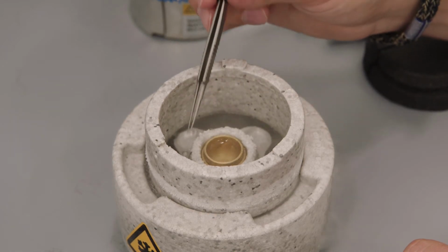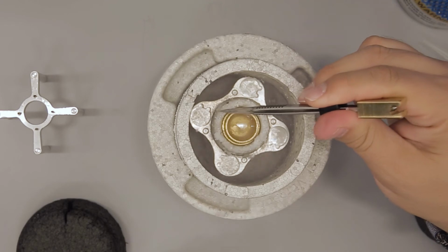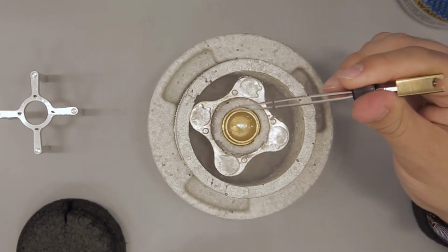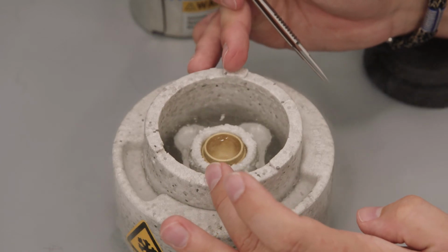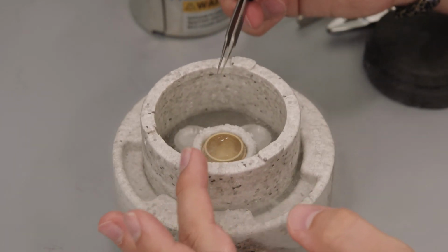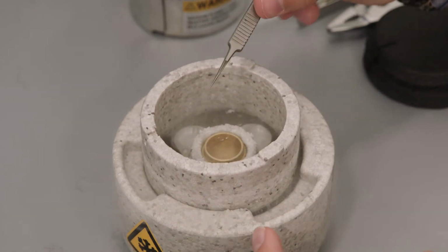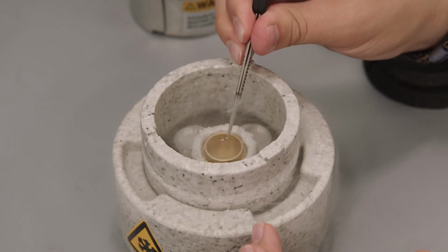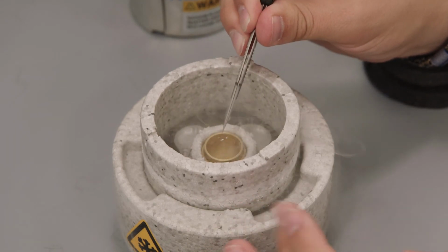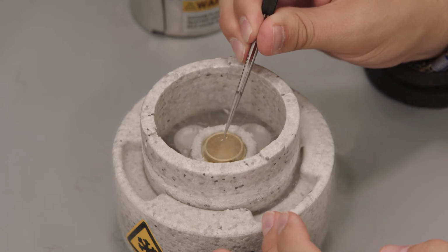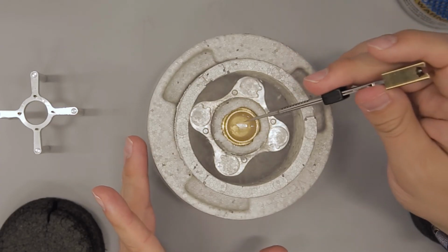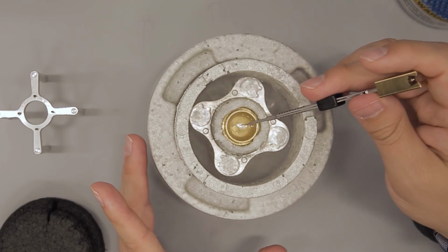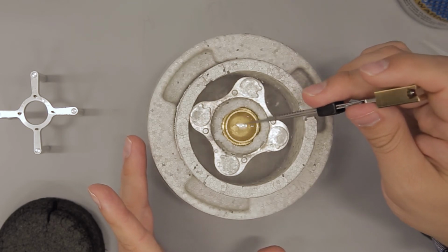So also the interface between the nitrogen vapor and the air is a source of contamination. And the lower your liquid nitrogen level is in your tray, and the lower this anti-contaminator ring comes, the closer it comes to your sample and the more chances you will have to get a source of contamination from that.